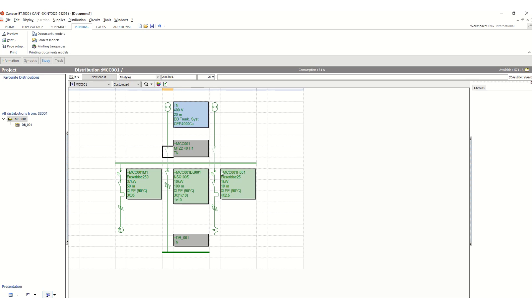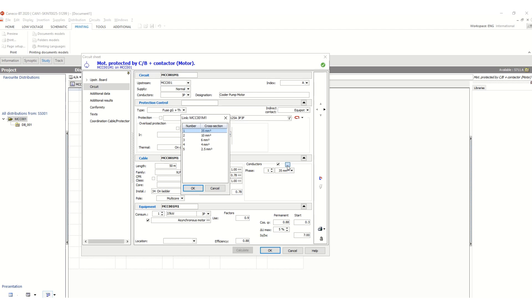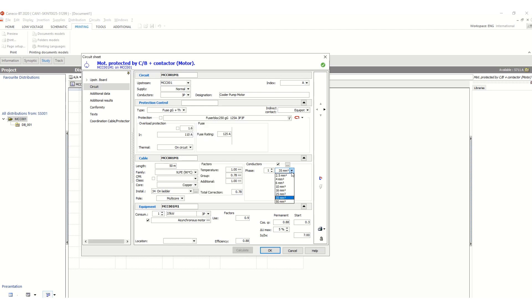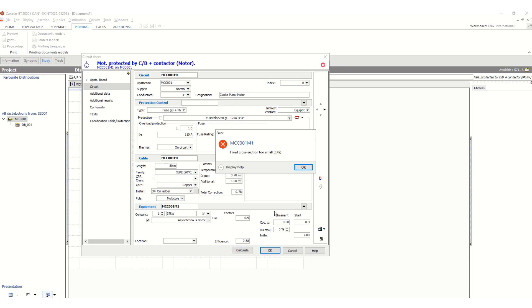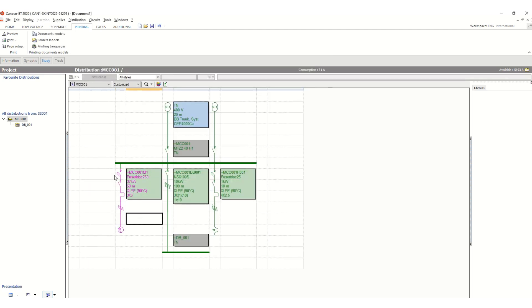One more thing — suppose this one, just double-click over here. As per the calculation it is coming as single core 35 square mm. If we select a lower size — instead of 35, suppose by selecting 6 square mm — let's calculate. A 'section too small' error warning is coming. Click OK and you can see this color has changed.